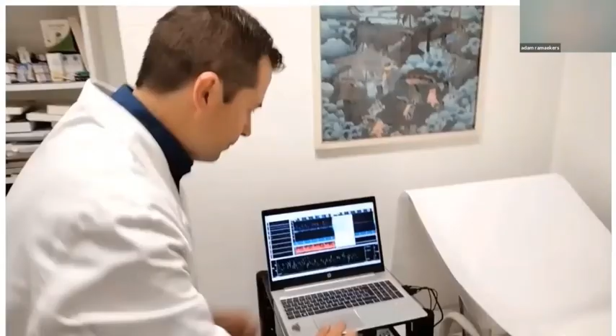This is the scan function. This function allows you to automatically perform a general scan of the window. In order to find the signal you're looking for, the feature allows you to choose from higher intensity, best signal, or highest velocity. And that's particularly important in clinical settings like stenosis and vasospasm. You can also select the angle scan, and the software can also automatically change the depth a bit in order to get a better signal.